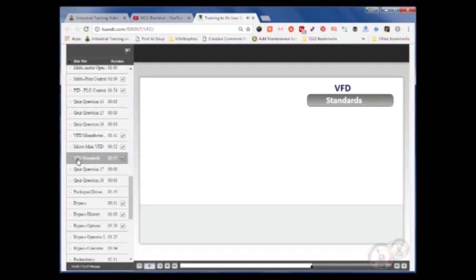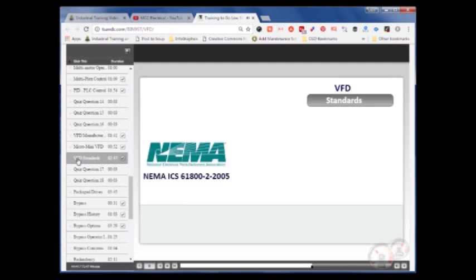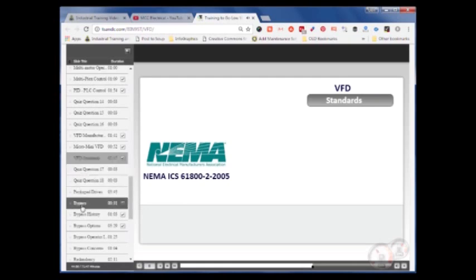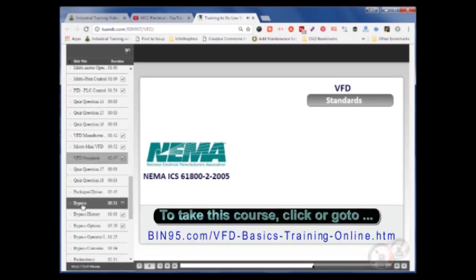Let's take some time to go over the standards that apply to variable frequency drives. NEMA, the National Electrical Manufacturers Association, has a standard titled NEMA ICS 61800-2-2005. This applies to general purpose adjustable frequency drives that include power conversion, control equipment, and an AC motor or motors. This also applies to systems connected to line voltage up to 1 kV AC, 50 or 60 Hz, and load side frequency up to 600 Hz.